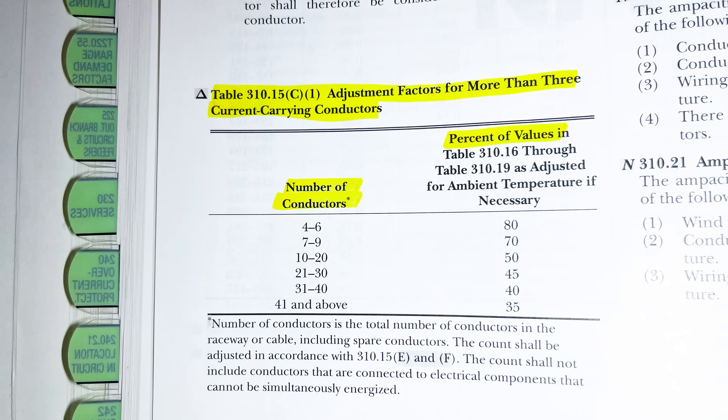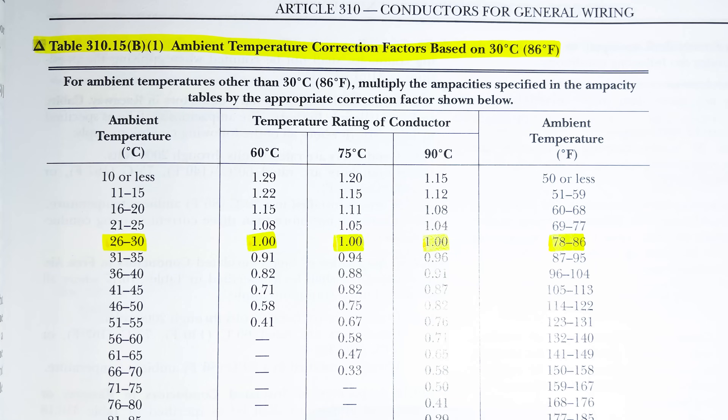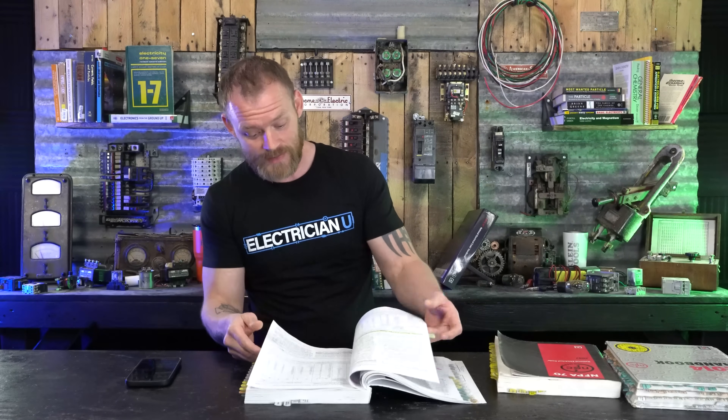Flipping back one page we have table 310.15(C)(1), adjustment factors for more than three current-carrying conductors. I highlight that one because you use it a lot — however many current-carrying conductors you have in a conduit, you may have to derate the ampacity. I even write in there 'does not apply to nipples' with '24 inches' in parentheses as a reminder. Then one more page back we have tables 310.15(B)(2) and (B)(1) — I highlight those titles so I know they are my ambient temperature correction factor tables.